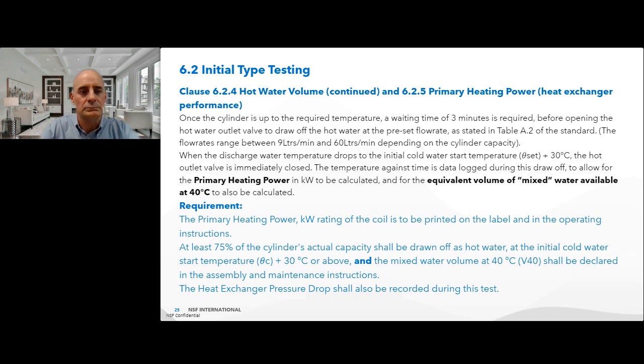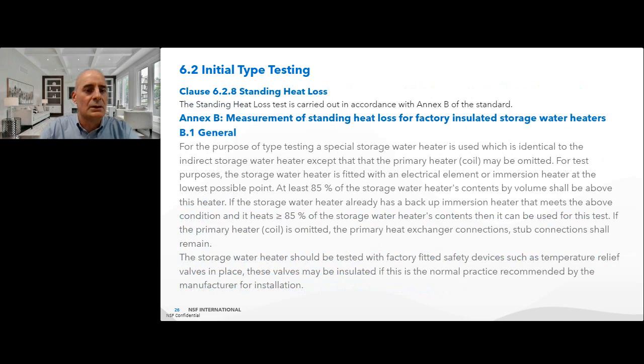Clause 6.2.8 then covers the standing heat loss test. The standing heat loss test is carried out in accordance with Annex B of the standard, and that is for the purpose of type testing, a special storage water heater is used, which is identical to the indirect storage water heater, except that the primary heater or the coil may be omitted.